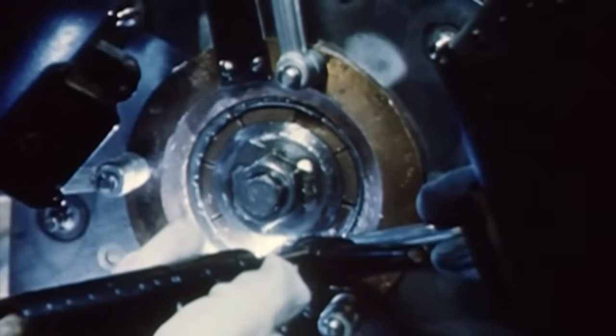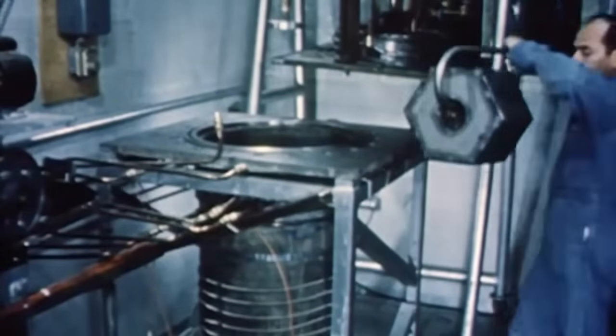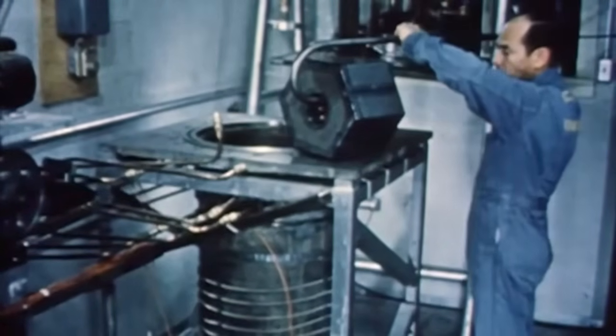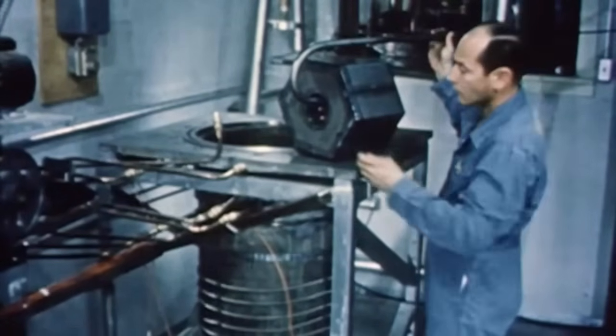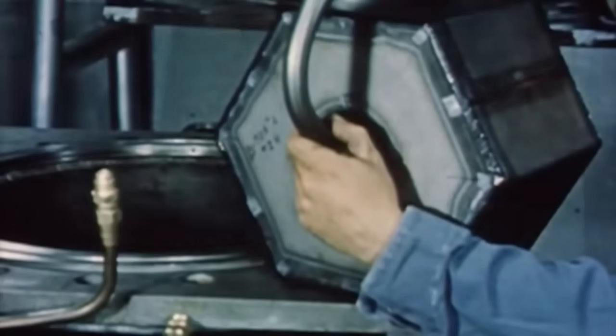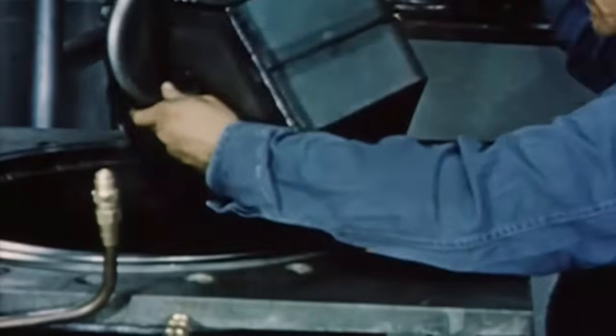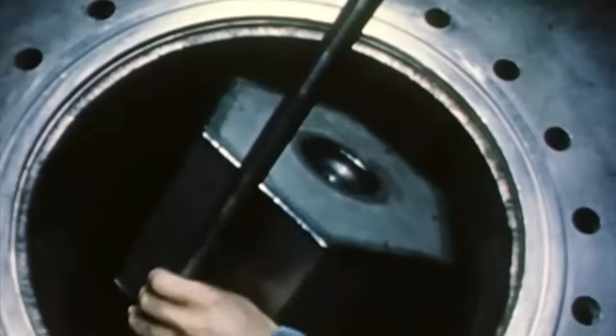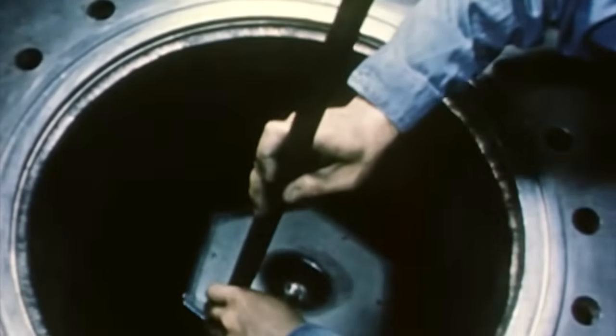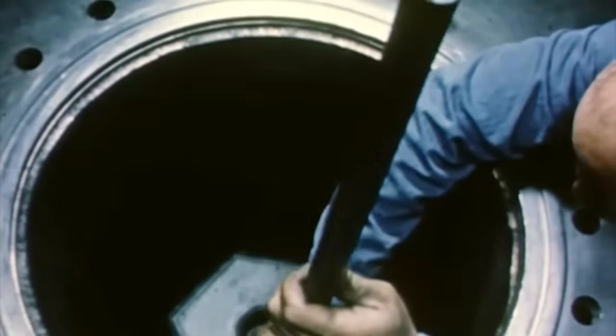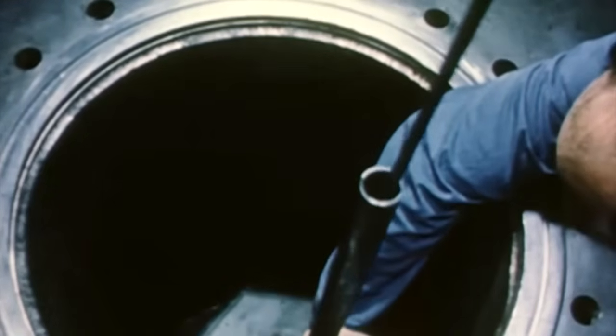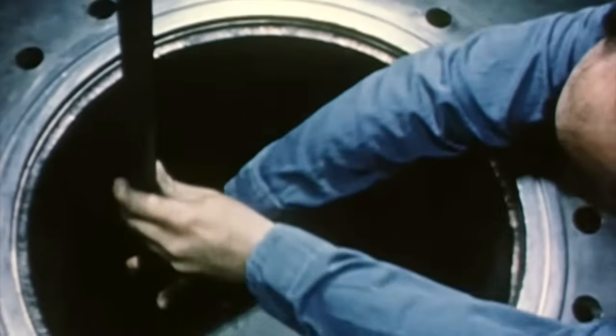Moderator can end cap welds were investigated through mid-1955. 10-inch sections of the cans were prepared for these tests. The object was to study the possibility of buckling or cracking of the head welds due to thermal stress, which might be encountered during reactor shutdown. The thermal stress was simulated in this test by mechanical cycling.